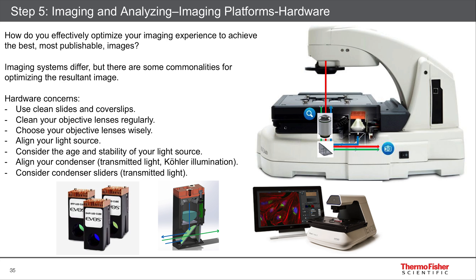However, what we sell here are the EVOS microscopes, which have a lot of great characteristics. There are no eyepieces, and it has a very short path length for the light, which means you get a brighter signal — and that's very important for a publishable image. It also uses a light cube. We sell EVOS light cubes with an LED lamp built right in. So there's no more aligning mercury bulbs, replacing them, or discarding mercury safely. The LED is built into the filter cube, giving you nice, even illumination every time without degradation — it's rated for 50,000 hours.